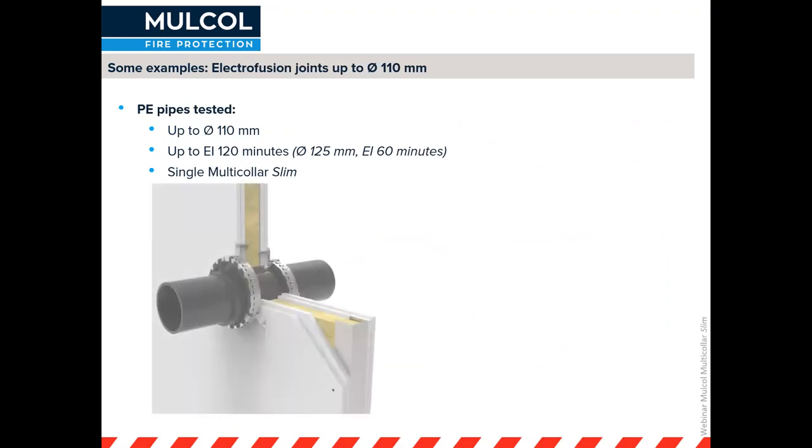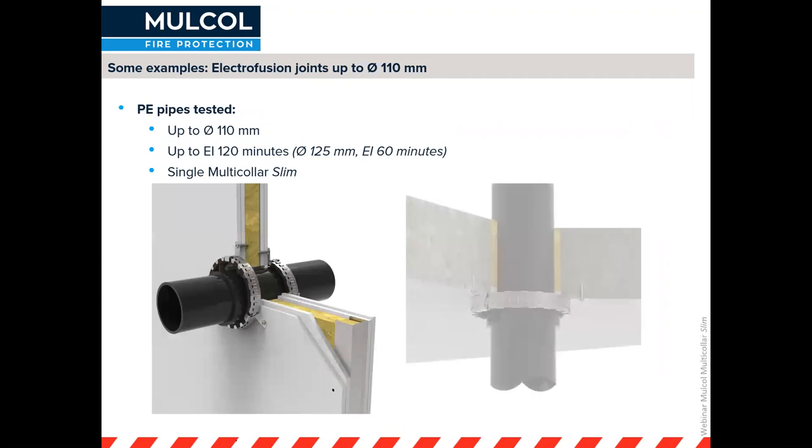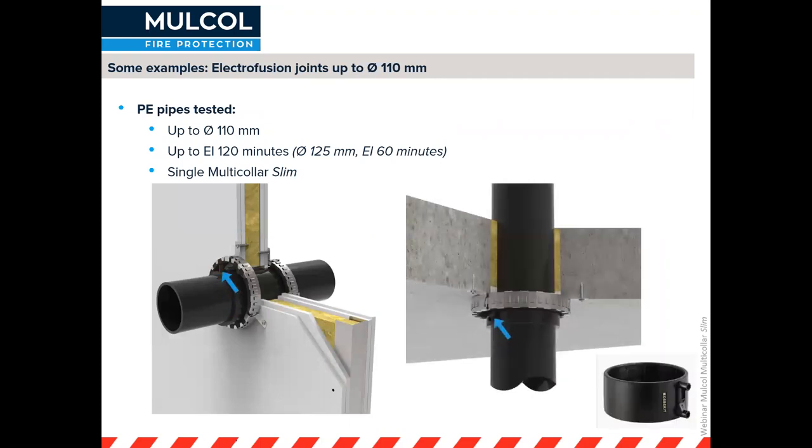Here is an example of the electrofusion joint. You can see the little nips on the coupling. Sometimes people try to remove these nips, but with the Multicollar Slim we have tested it with the nips still on — so you don't need to break anything off. We've tested 60 minutes for 125 millimeter pipe and 120 minutes for 110 millimeter pipe with these electrofusion couplings.